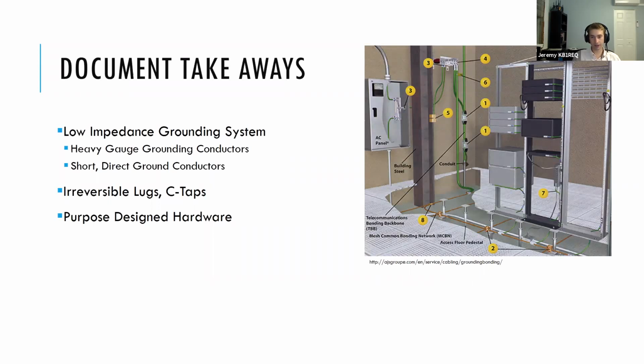Short and direct grounding conductors, making them as short as possible and making them as direct as possible, straight line, rather than kind of cable routing that we might be used to with other cables. You want that to be as short and direct to your grounding bus bar as possible. A term you see a lot when it talks about connections is irreversible. So when you're talking about lugs for grounding, C-taps for joining two conductors together, something they emphasize is mechanically, those have to be irreversible.